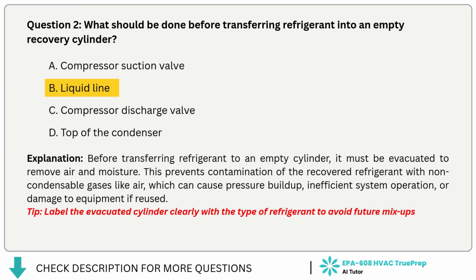This prevents contamination of the recovered refrigerant with non-condensable gases like air, which can cause pressure buildup, inefficient system operation, or damage to equipment if reused. Tip: label the evacuated cylinder clearly with the type of refrigerant to avoid future mix-ups.